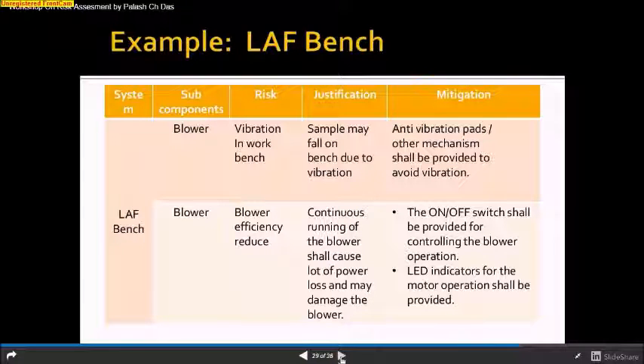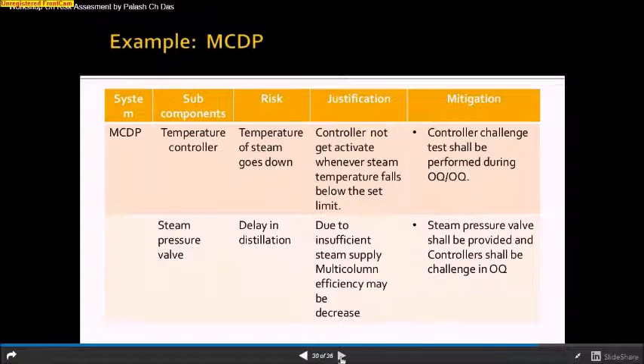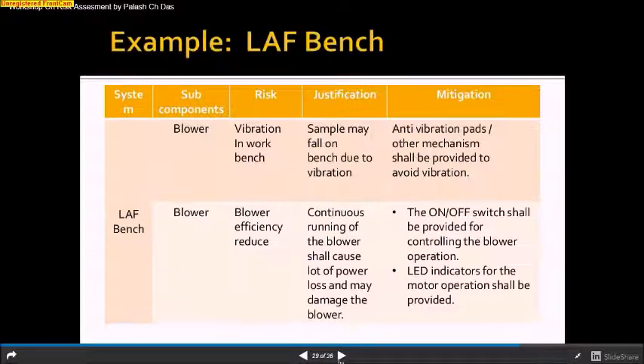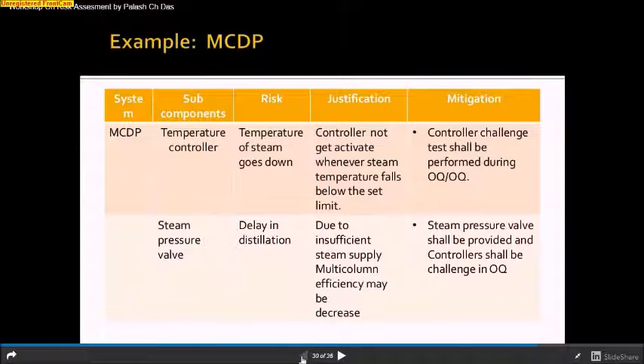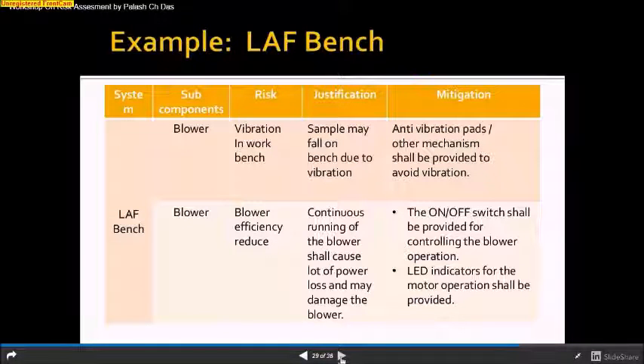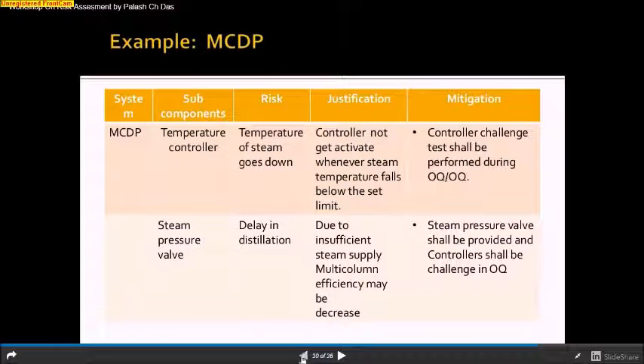MCDP is nothing but the generation system of WFI. So we know the subcomponent temperature controller is a very important part of MCDP. The temperature of the steam goes down if it is not working properly. The justification controller does not get activated whenever the steam temperature falls below the set point. So a controller challenge test shall be performed in IQ, and periodic preventive maintenance shall be done to know whether the controllers are in good condition or not.